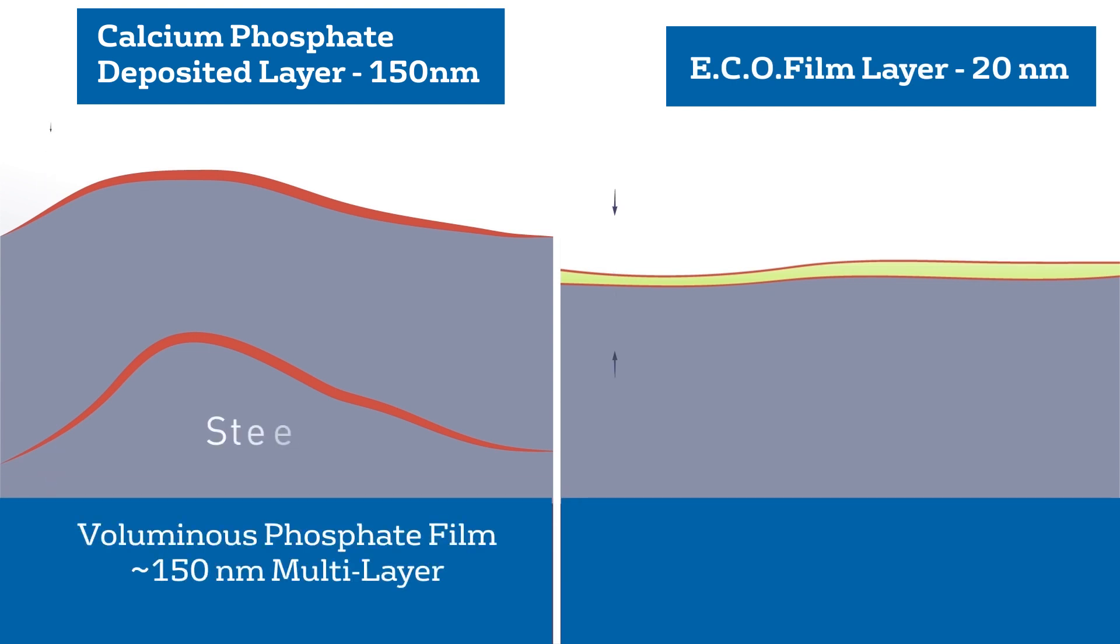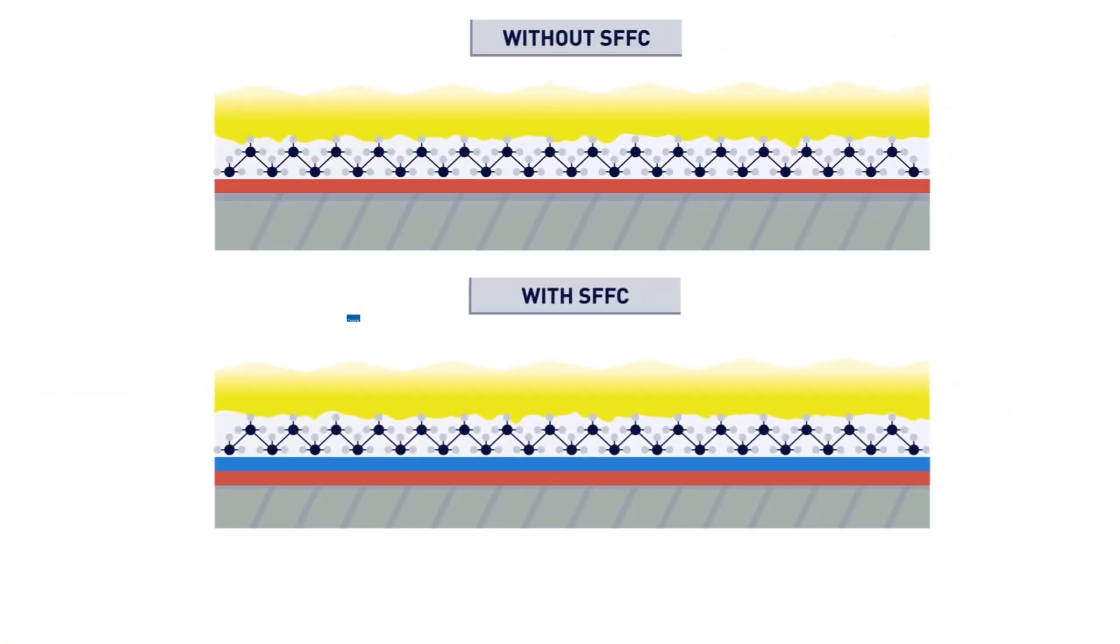Ecofilm programs auto-limit film growth, leading to a layer that is roughly 20 to 50 nanometers thick, about a third of the thickness of a protective film in a phosphate program.